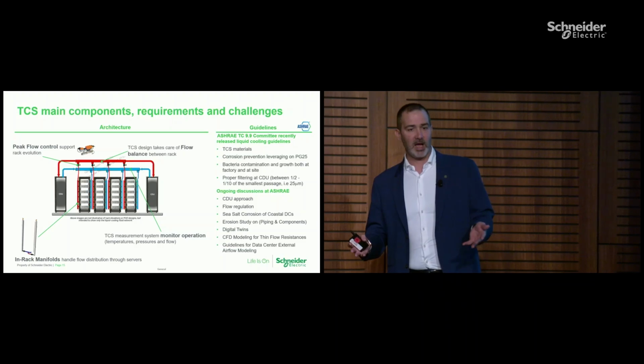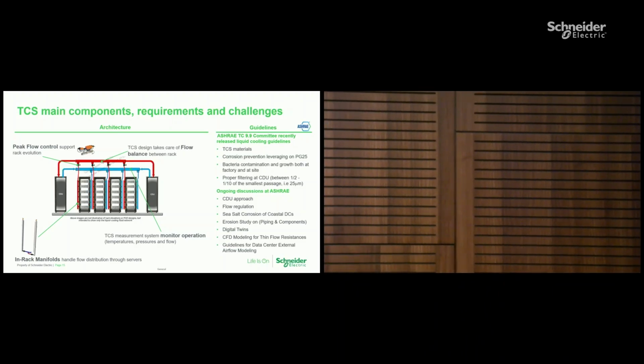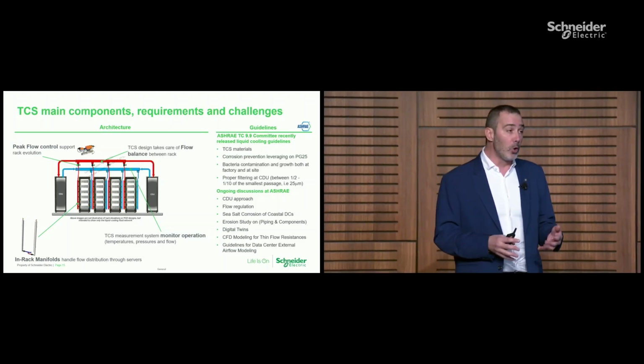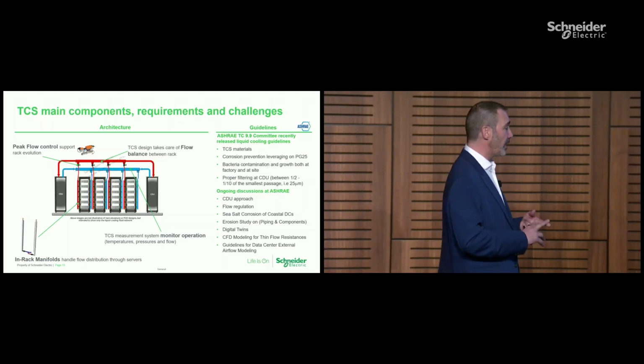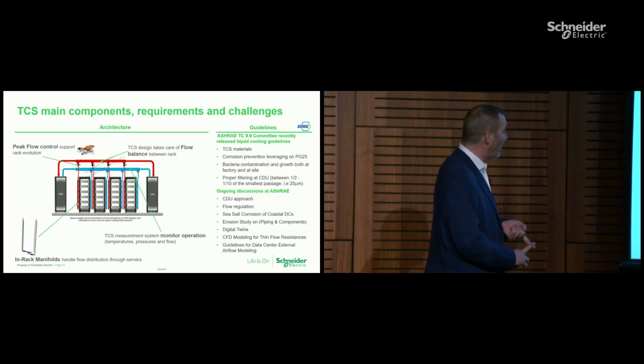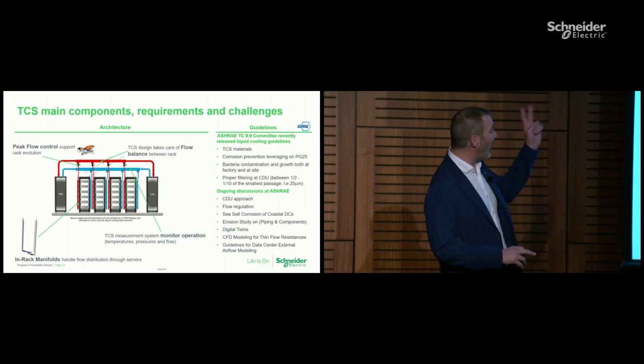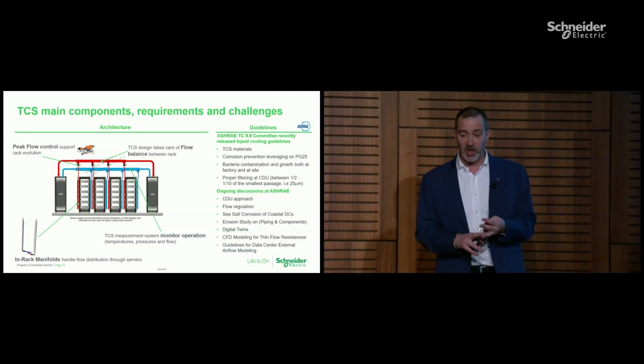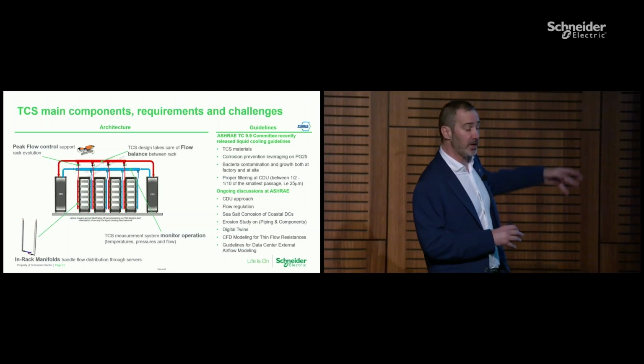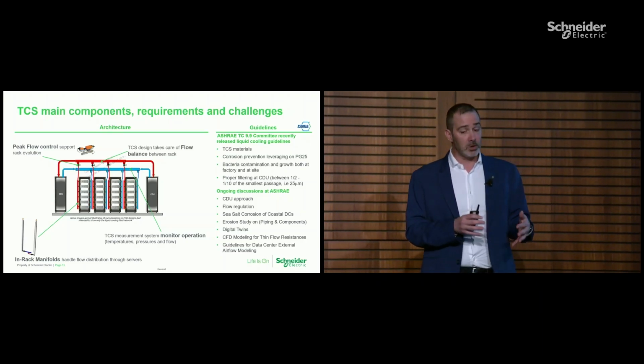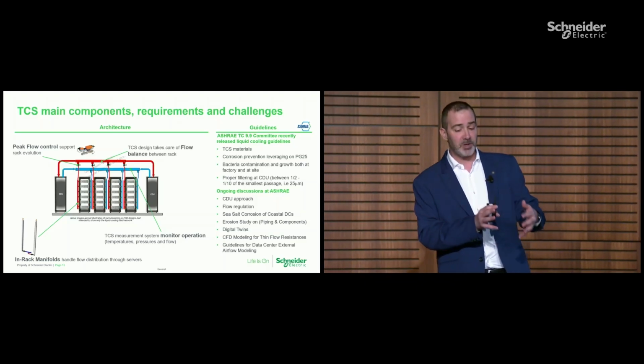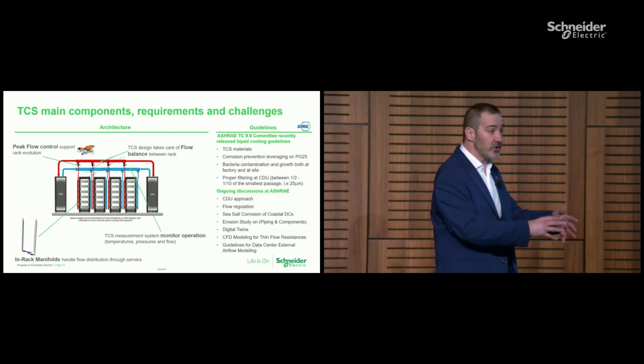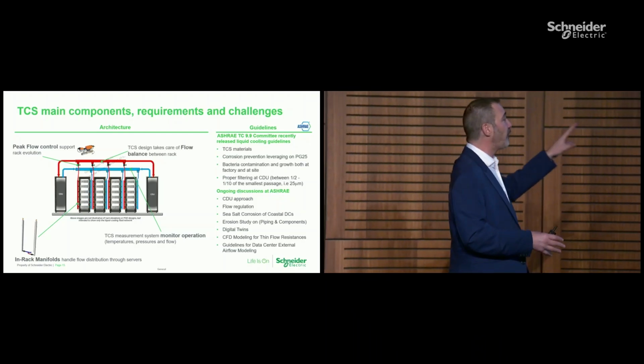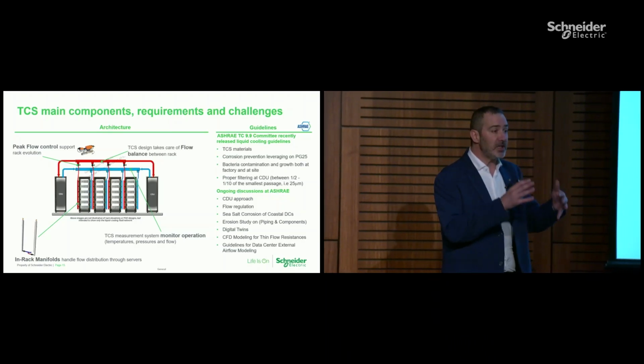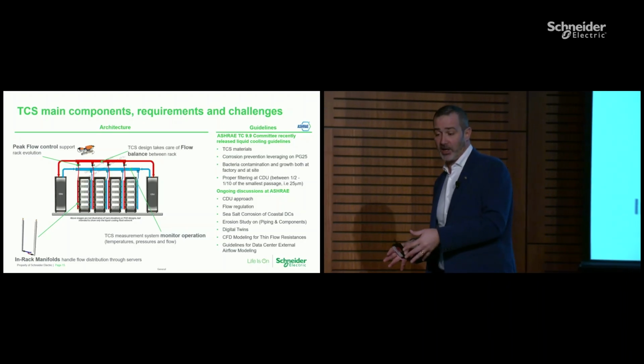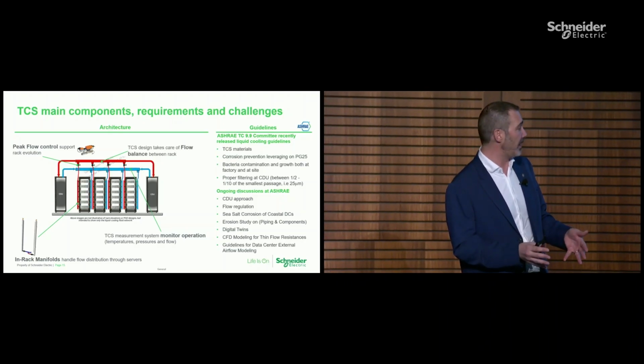Unfortunately, this is not just like that. A design around the TCS includes the manifold on the back of the server, on the back of the rack, which distributes the fluid. It includes the valves to regulate, the monitoring system. All of these are part of an architecture, which is not only related to specific areas, not only specific pipework. So that's a full architecture, an architecture where many guidelines and recommendations are happening.